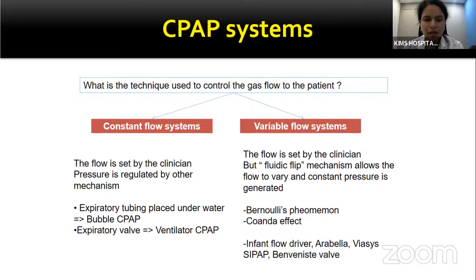So the flow is constant and the pressure can be regulated by the clinician by increasing the depth of immersion of the expiratory tubing in bubble CPAP or by increasing the resistance offered by the expiratory valve in ventilator CPAP. In variable flow systems, such as infant flow driver CPAP, the flow is set by the clinician, but the fluidic flip mechanism, because of one limb of CPAP which is open to the atmosphere, allows the flow to vary between inspiration and expiration, and hence constant pressure is generated.